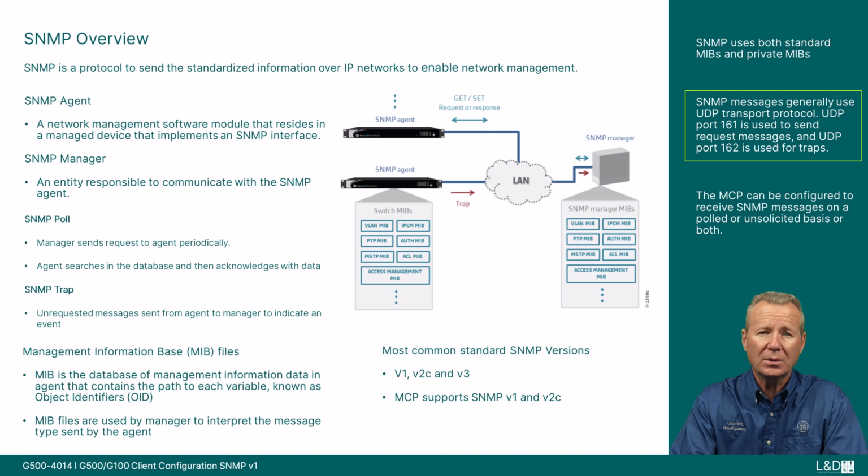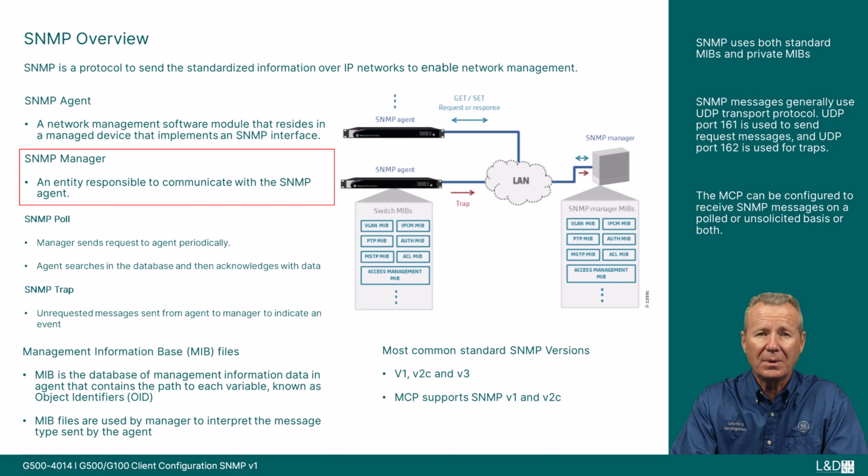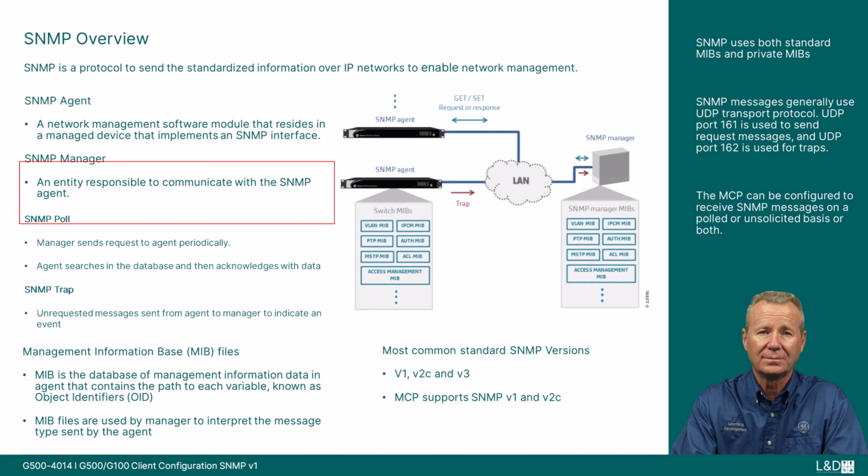Some important SNMP concepts are worth mentioning before continuing, such as SNMP Agent. The SNMP Agent is a network management software module that resides in a managed device that implements a SNMP interface. Downstream IEDs that support the SNMP protocol in this context are SNMP agents. SNMP Manager. The SNMP Manager is an entity responsible to communicate with the SNMP agent. MCP Gateway in this context is a SNMP Manager.